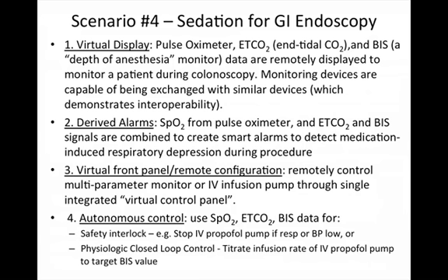Or perhaps one level of increasing sophistication here would be the implementation of physiologic closed-loop control. That is, instead of only stopping the infusion with a safety interlock, one would restart the infusion and titrate or adjust the infusion rate of the sedative medication to achieve a target value, perhaps on the depth of sedation monitor. So that's a description of the 4 discrete levels of interoperability from a risk standpoint, a complexity standpoint.